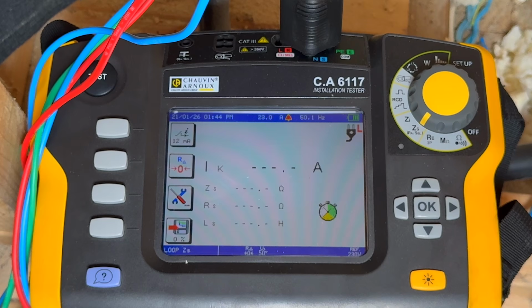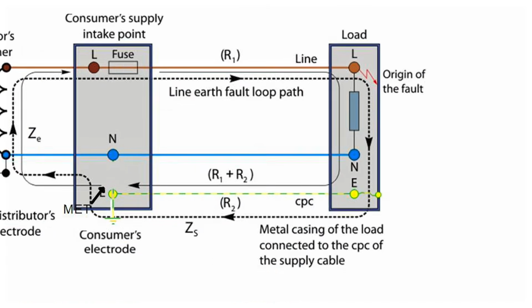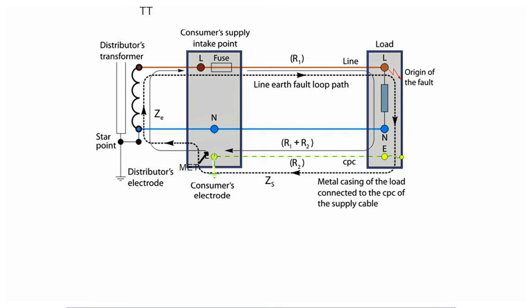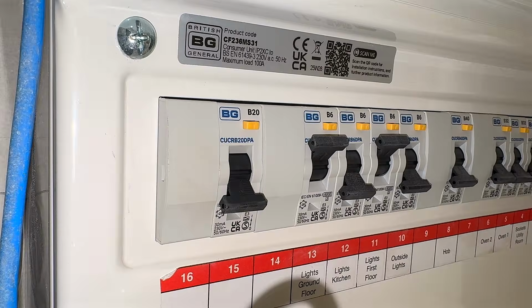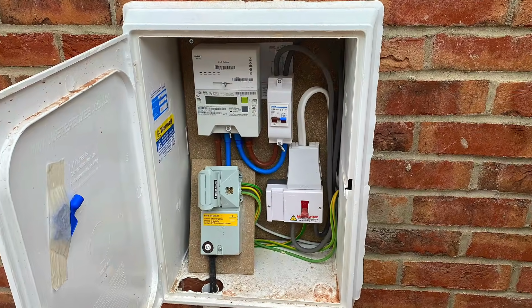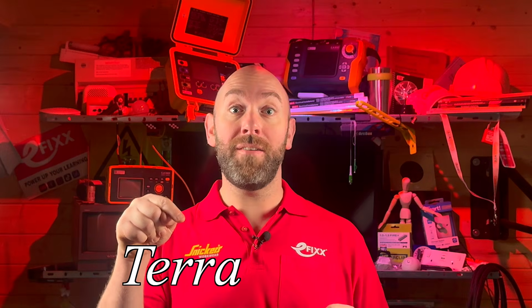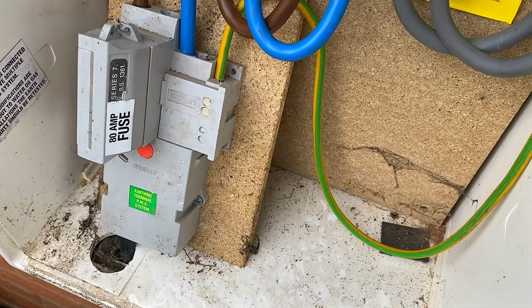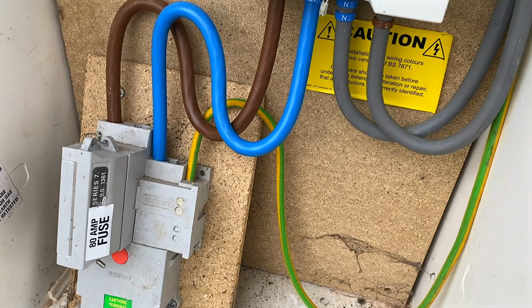So what happens when a fault occurs, and how does that overcurrent protective device know when to trip when it does? Well, for that we need to understand the earth fault loop path. Where a fault occurs, perhaps in an appliance, the fault current travels back through the earthing conductor, back to the supply transformer, through the windings and back down the line conductor to disconnect the overcurrent protective device, and on a TN system do all that within 0.4 of a second. The difference here is TN, terra neutral. This is where the earthing conductor and neutral are combined, which makes a more secure path back to the source. TT does not have that.